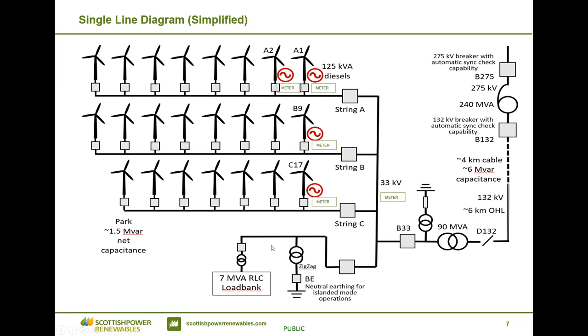And then at the bottom, you can see what we used as auxiliary equipment for the whole test. It was a load bank, and we had a capacitor and inductance included there, and an earthing transformer. B33 is the main breaker of the wind farm, which connects the wind farm to a 90 MVA transformer.